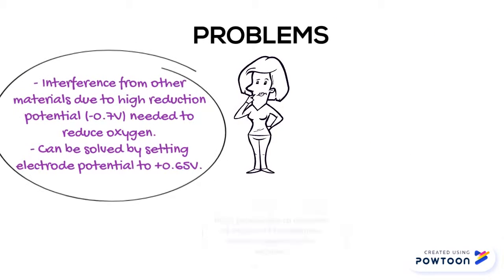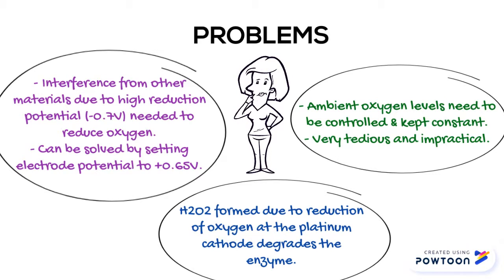There are three problems with the first generation biosensor. The first problem is interference from other materials due to the high reduction potential needed to reduce oxygen; it can be solved by setting electrode potential to positive 0.65 V. The second problem is that hydrogen peroxide from the reduction of oxygen at the platinum cathode degrades the enzyme. The third problem is that ambient oxygen level needs to be controlled and kept constant, which is very tedious and impractical.